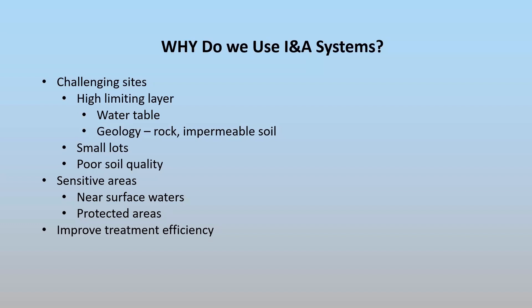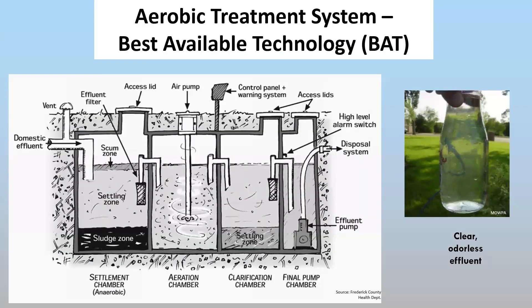We have what's called an advanced treatment unit, also known as best available technology or BAT in Maryland. These are basically almost like a miniature wastewater treatment plant. The unit replaces a septic tank and provides some of the same functions as a passive septic tank, but also adds the important addition of aeration. That aeration is key to providing beneficial bacteria in the system to help break down nutrients and organics.